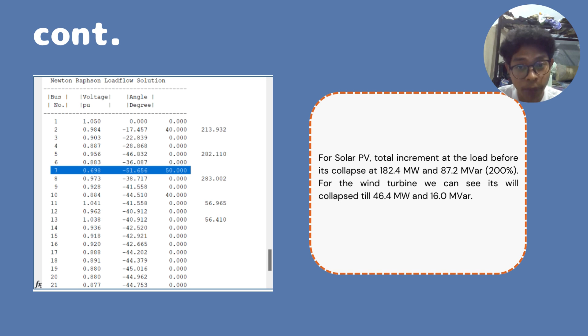So for the integration of the solar PV, the total increment of the load that we can do is actually 182.4 megawatt active power, and also 87.2 megavar for reactive power. The increment of the load that we can do is about 200%. This is because in this simulation we have changed the load of the bus data. We times it by 2, and it will get 100% increment. So for the PV solar, we have reached 200% at bus 7, and after the next increment, we get the collapse data, which is below the range that we have set, which is from 0.9 to 1.1 pu. So we will go next.